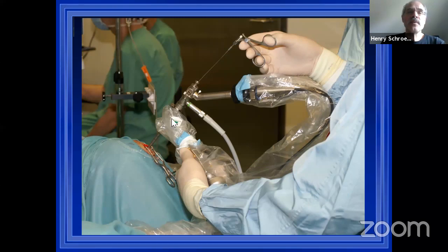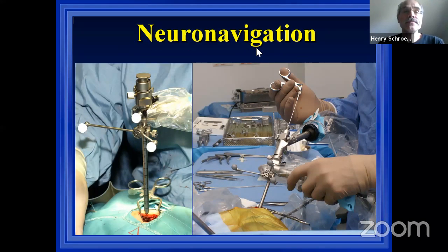What I see frequently when people start with the endoscope is they bend the instrument in the shaft because they want to have the instrument go left or right. But of course, it's not working because the instrument is within the working channel of the endoscope. So with the left hand, you guide the instrument left side, right side, up, down. With the right hand, you only control the depth, how far you go in, and you can open and close it. But this is completely normal. You look at the screen and then you want to move your instrument left, right. This is one important step that you need to learn.